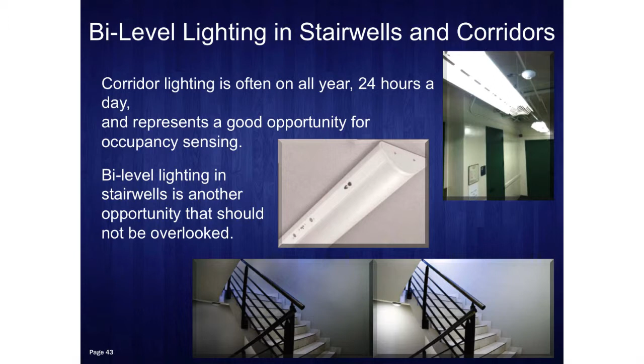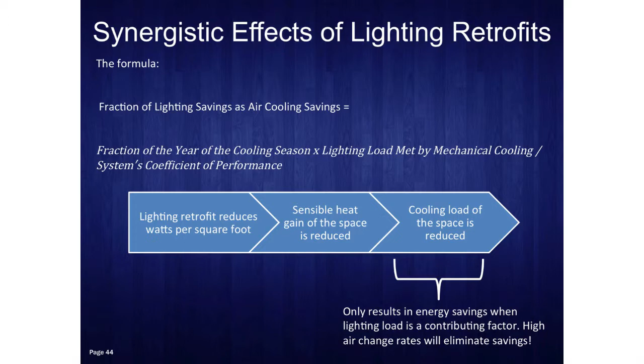And then, of course, you have synergistic effects. Right now you probably like the fact that your lights pump out lots of heat because your spaces are cold. For us and our climate, we're constantly fighting the cooling issue, not so much the heating issue. So for us there's a huge synergistic effect from reducing that lighting power density and getting those watts out of the space. Again, mileage may vary, but here's the formula you can take away to figure that out, taking that fraction of the year of cooling into account to get those synergistic effects.